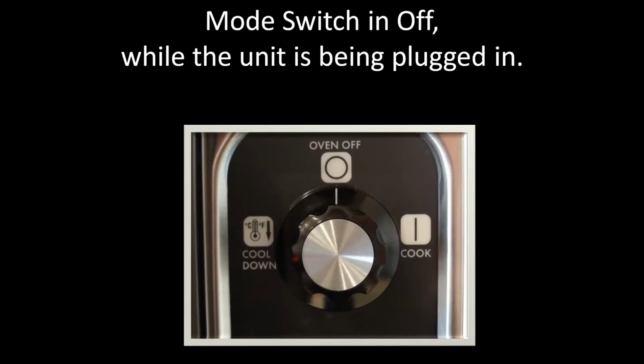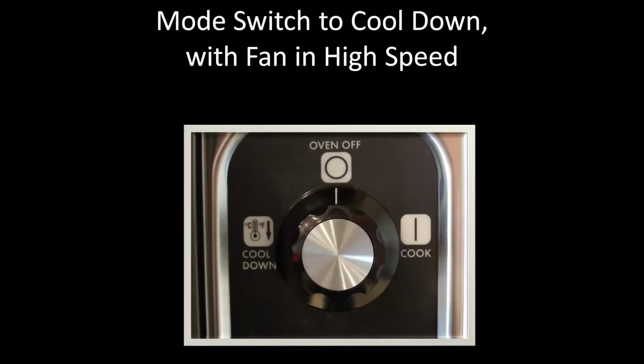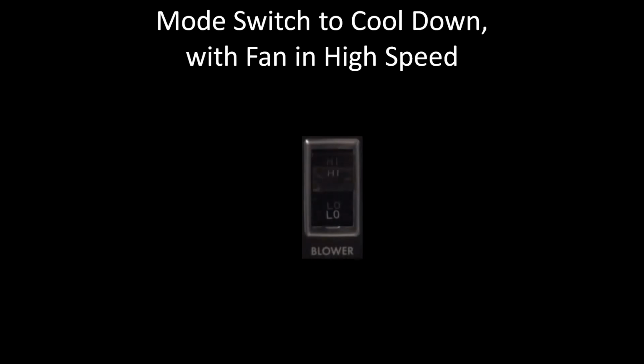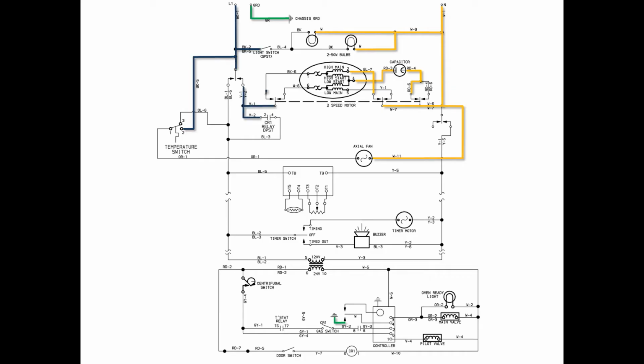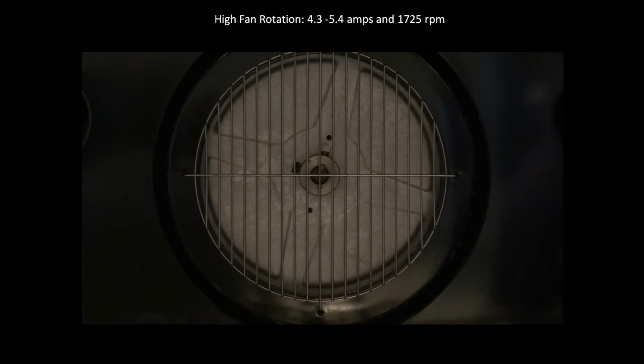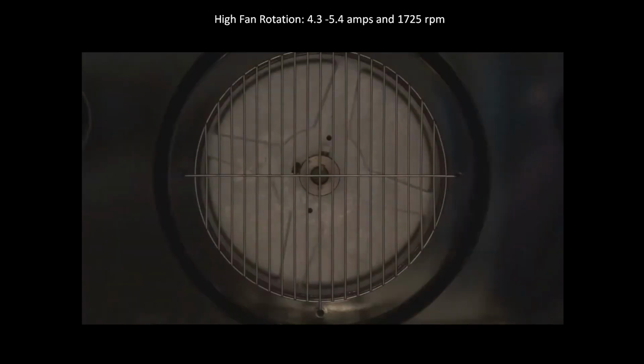We will start by looking at the diagram with the unit off and the cord being plugged in. When power is applied to the unit in the off mode, it will be present here. Now we will put the unit into cool down and put the fan into high speed. Here we see the mode switch pass voltage to the fan speed switch, which feeds the motor high winding. This causes the motor to rotate in a clockwise direction at 5.4 amps and 1,725 RPMs.